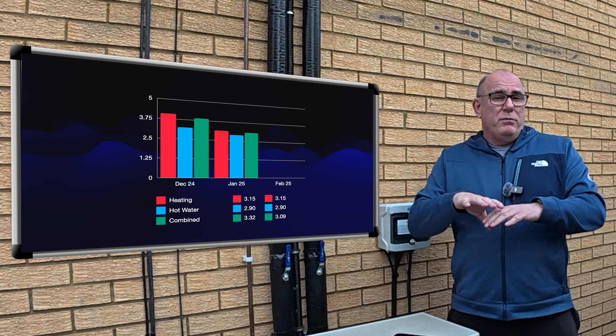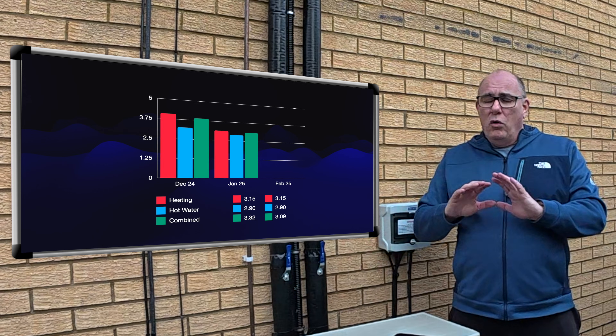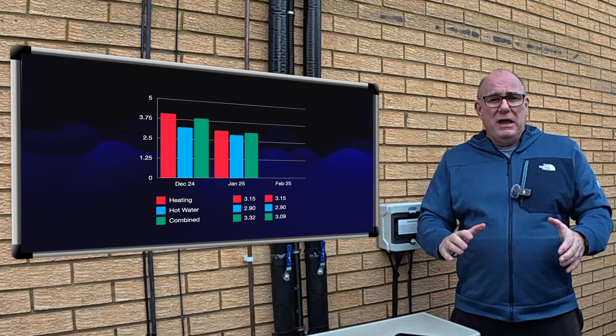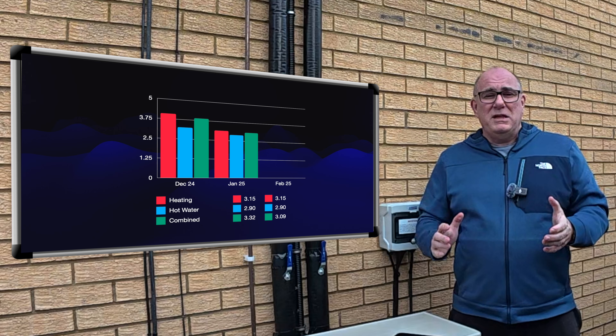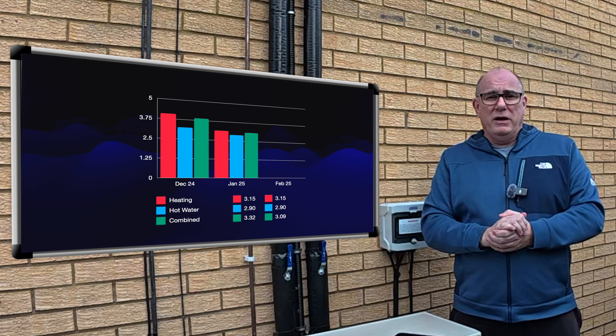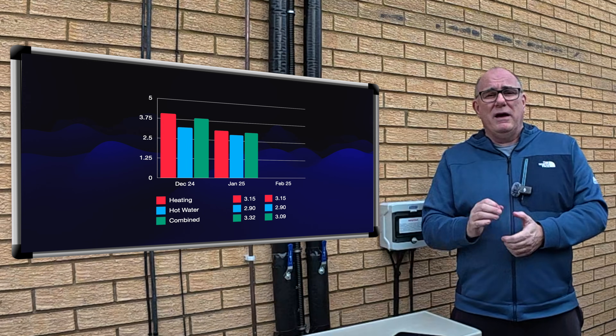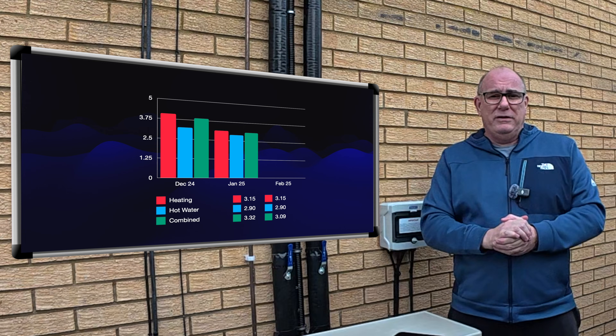If we use the Daikin app to keep everything equal so all the numbers are the same, using the rounding errors built into the Daikin app, we can see a coefficient of performance for both hot water and heating of 3.09 — down ever so slightly from the more accurate combined reading of 3.32.